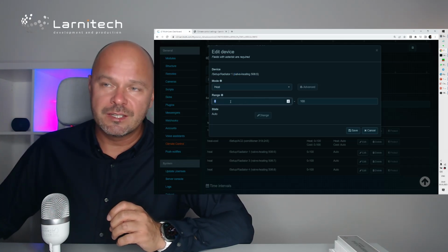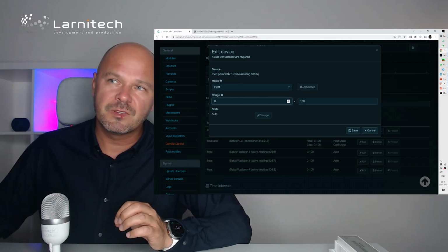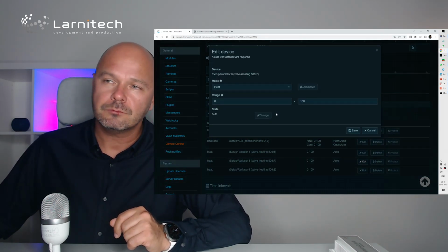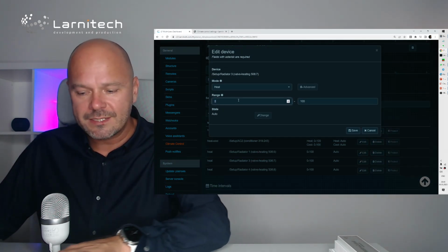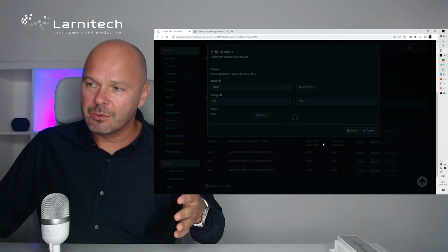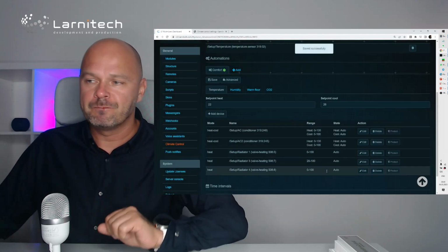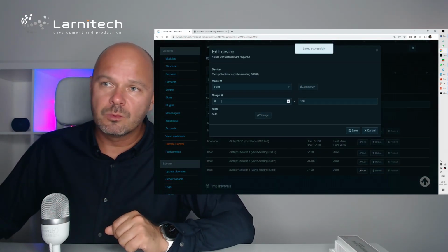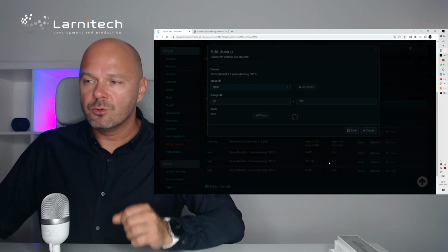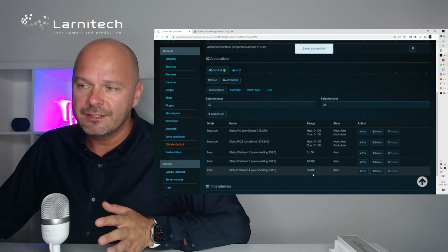So this radiator will work only if the first one will work 0-100. Okay. The second one will work from 20 to 100. So if more than 20, they will both work. If less than 20, only the first one will work. And the third one will work 50 to 100. So all three will start working if we need heating more than 50%.